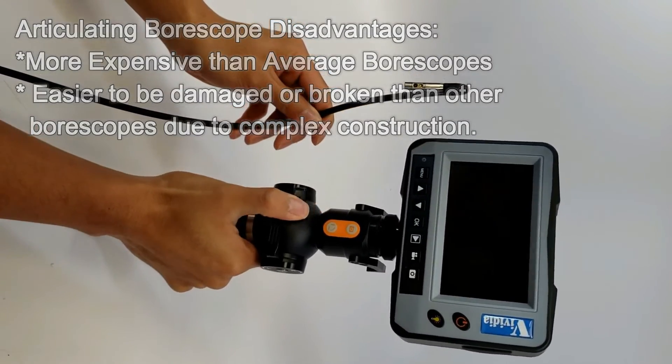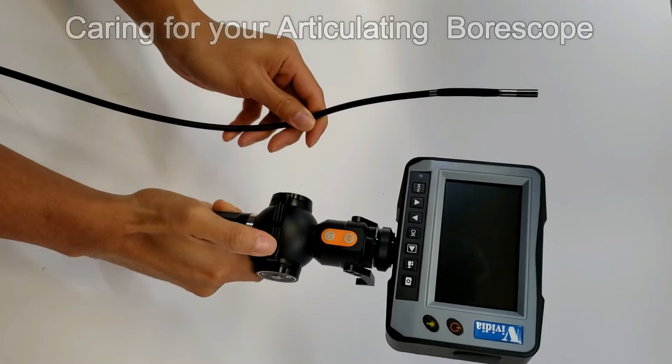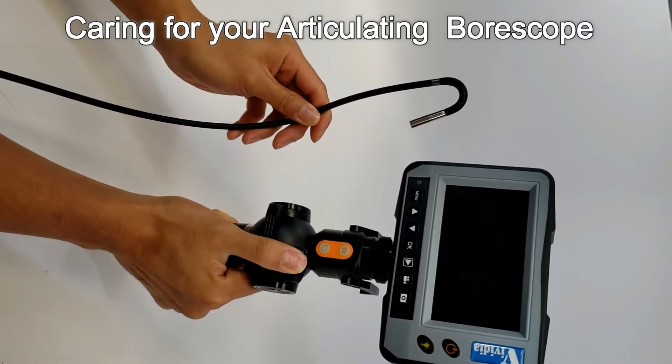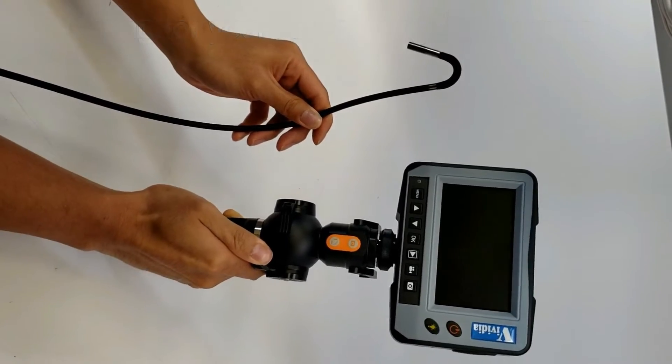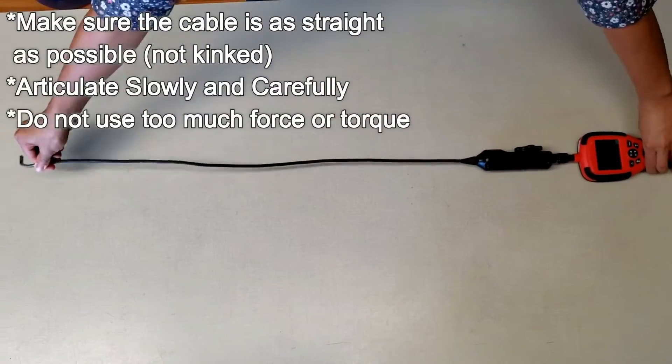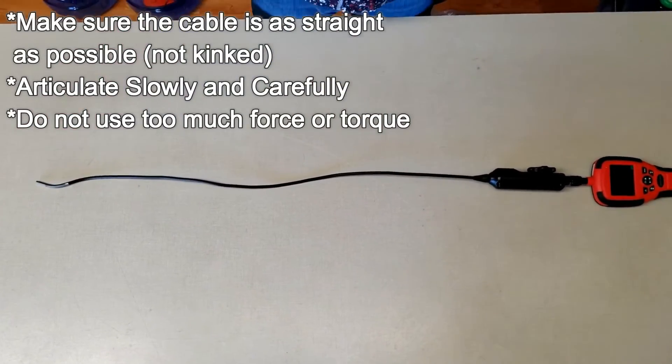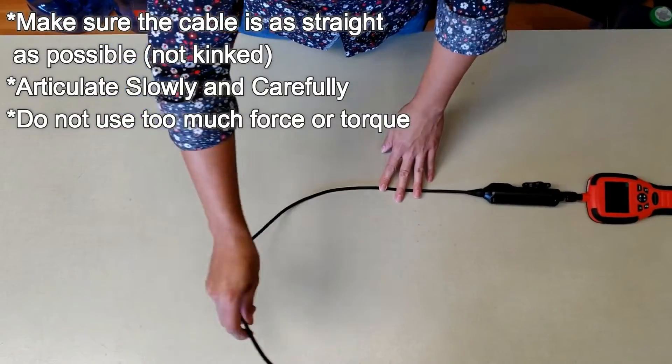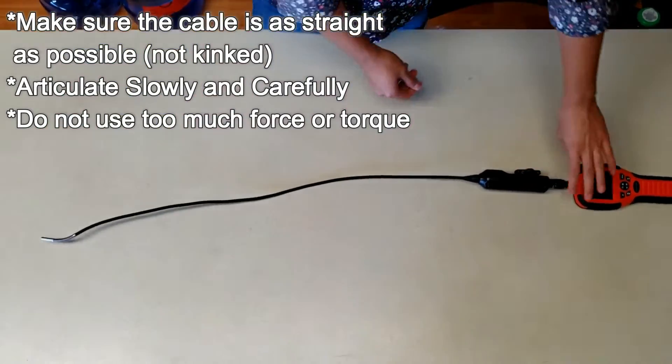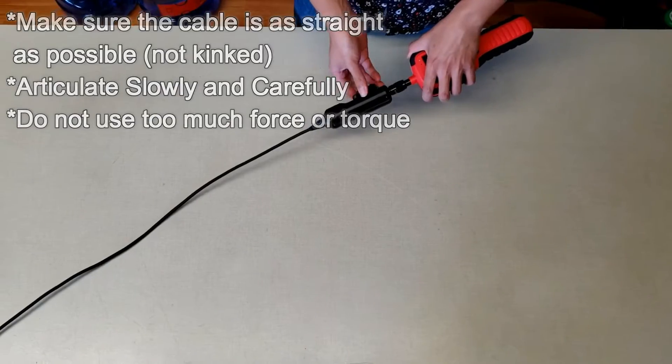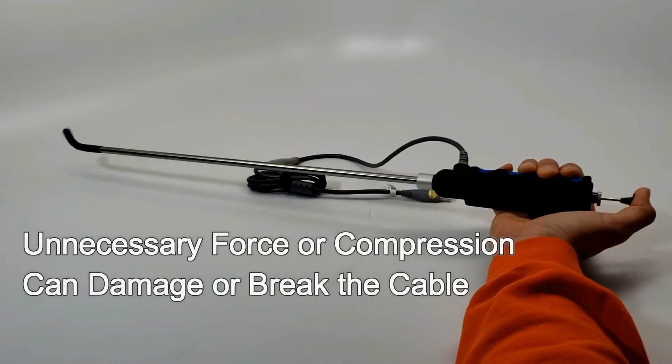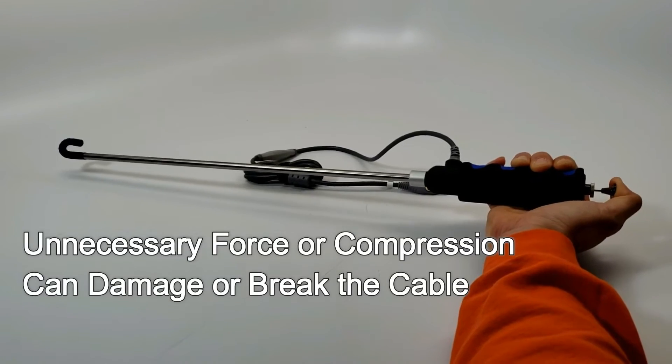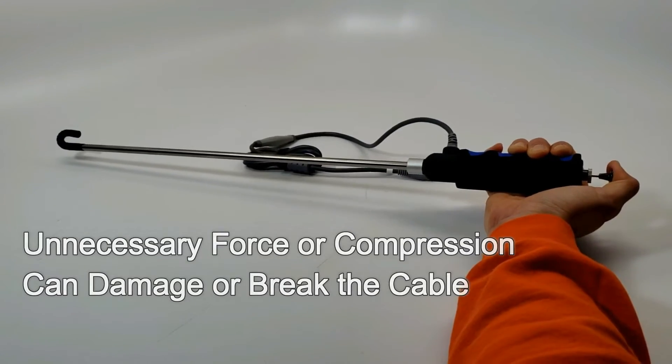Boroscopes are built to be sturdy tools, but they also have delicate electronic components and must be cared for just like any other device such as your smartphone. Take care to make sure that the probe is straight as possible, avoids hard impact, and is articulated slowly and carefully without using too much force when bending the cable back. Unnecessary compression can stress the cable causing it to break immediately or gradually over time.